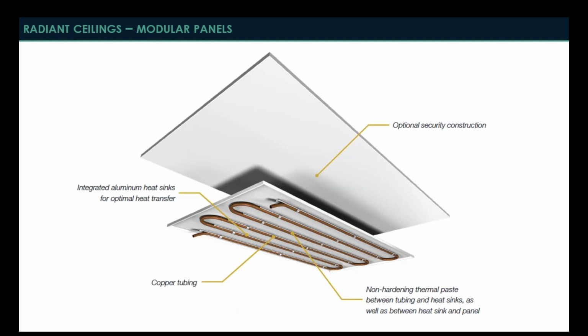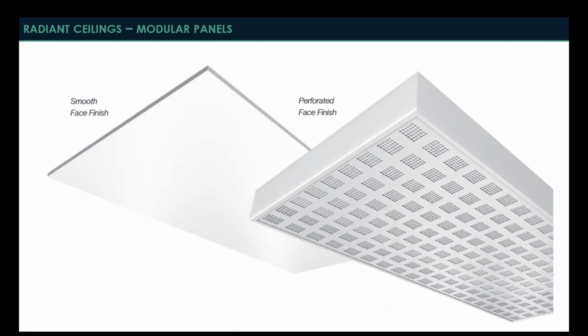They're going to come in standard sizes, whether that's 2x2, 2x4, 2x6, 8, 10, etc. And the modular panel is really meant to fit in a normal ceiling grid. And the way that they work is they have copper tubing run on top of the panel, and that copper tubing is then connected directly to the aluminum or steel panel via heat sinks and what is known as thermal paste. So the heat sinks and the thermal paste are very important because it enhances the energy transfer from the fluid running in the copper tubing to the panel itself.